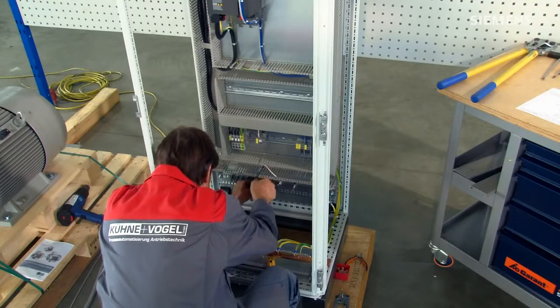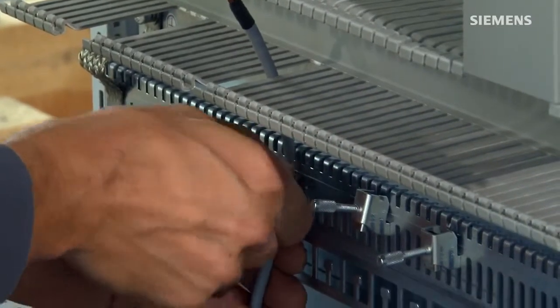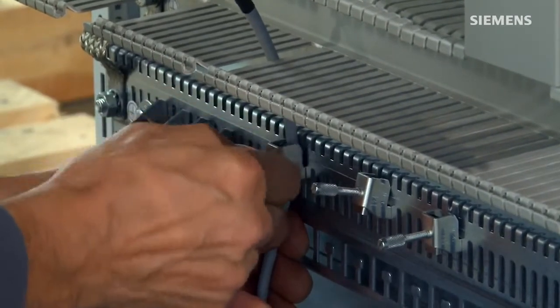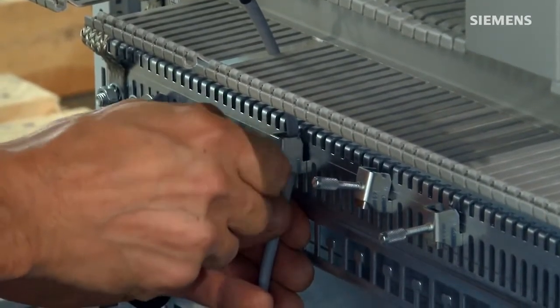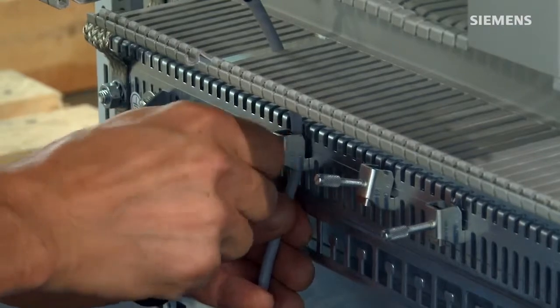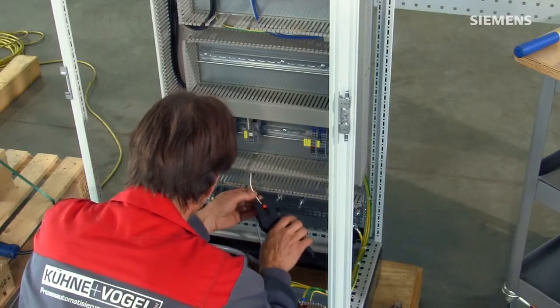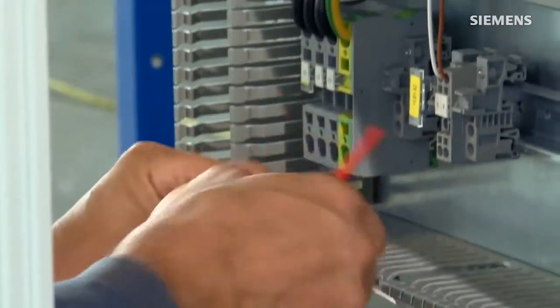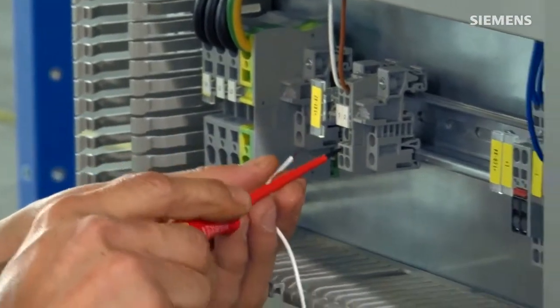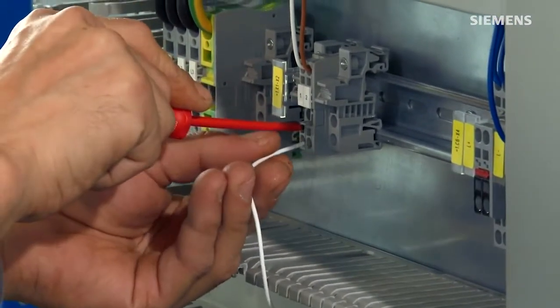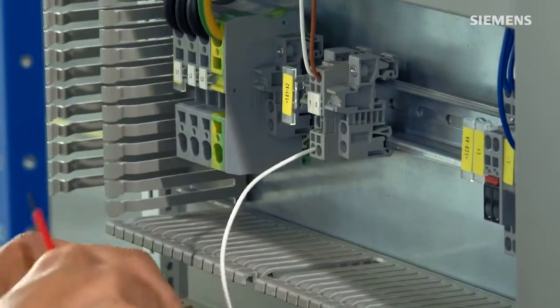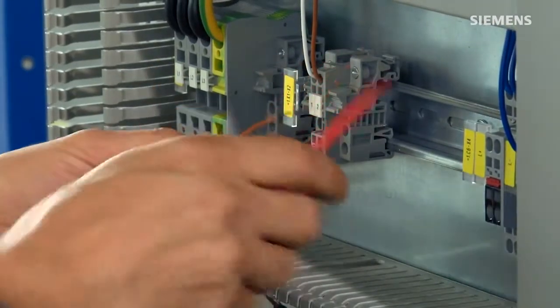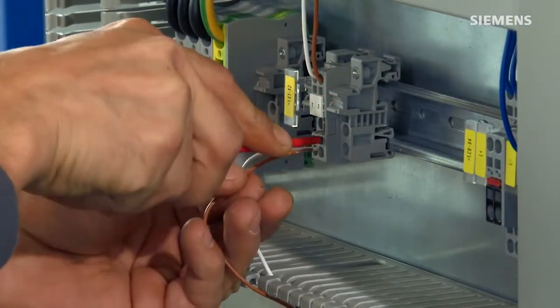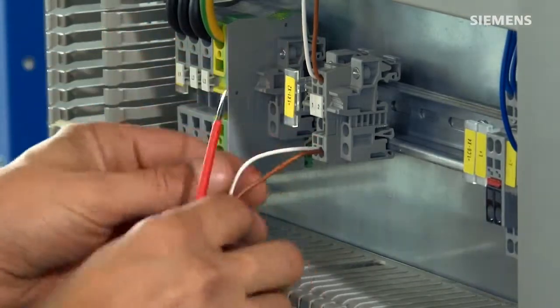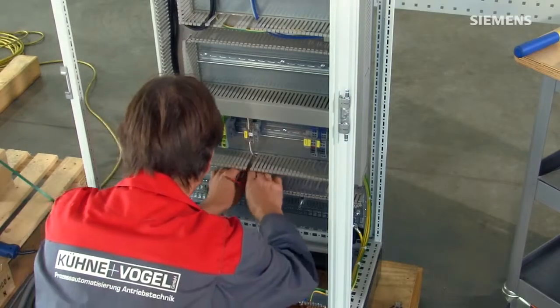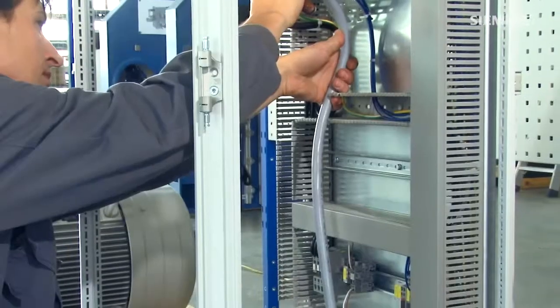Using a bolt clamp, place the cable on the EMC rail and tighten the clamp. Strip the cable and attach it to the terminal strip provided for this purpose. Now let's move on to the motor cable.